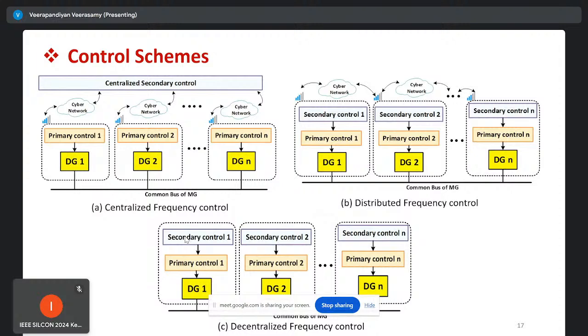In general, a microgrid has several control schemes. Conventionally, we have centralized control schemes. Any device or distributed generator in a microgrid will have its own local control, called the primary controller. In addition, there is a secondary controller which helps maintain the voltage and frequency of the system.